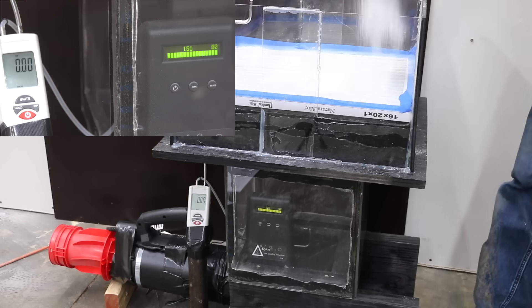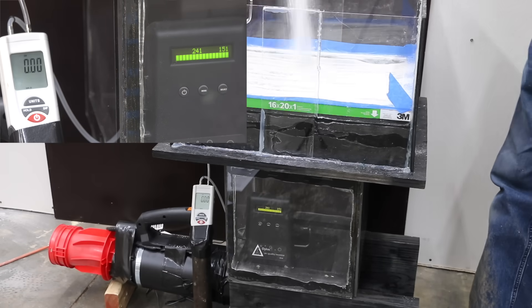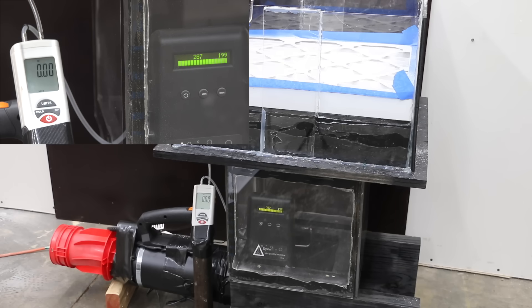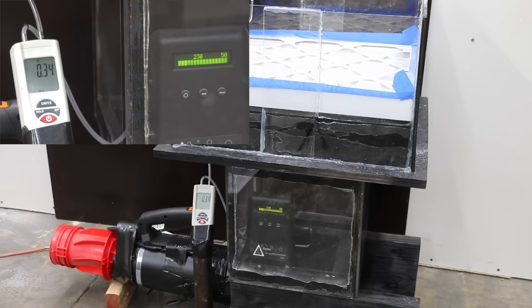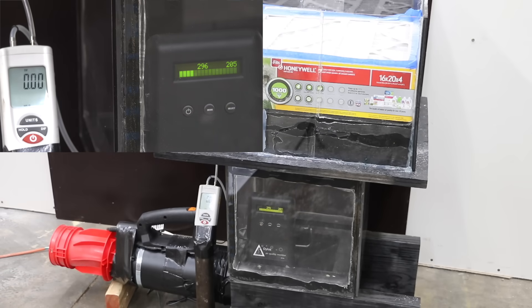Natural Air didn't do as well as the DuPont, Aerostar, or Nordic Pure, with 6,600 small and 5,500 large particles, and really struggled with a static pressure of 1.07. The 3M 600 did by far the best yet at 500 large and 400 small particles, but as expected had a very high static pressure of 1.31. The 4-inch Honeywell did even better at just under 300 small and around 200 large particles, with the best static pressure yet at only 0.34, showing a lot of life left in the filter.